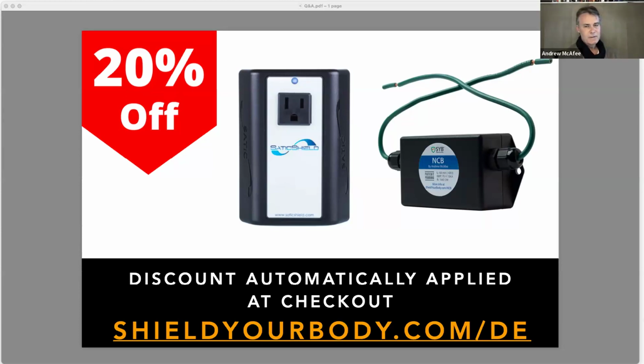Yeah, the surge protection versus GFCI, I don't see a compatibility problem with using a filter on it. I don't think the filter system is going to shunt so much to the grounding conductor. It's going to be more than 5 milliamps? I have a hard time believing that. I agree. I read an article that one of them was kind of smart, and it literally communicates almost over the Internet of Things. That particular model might have an issue, but the ones that 99.99% of us use, no, not at all. They trip so easily that the Satic wouldn't interfere with it at all.